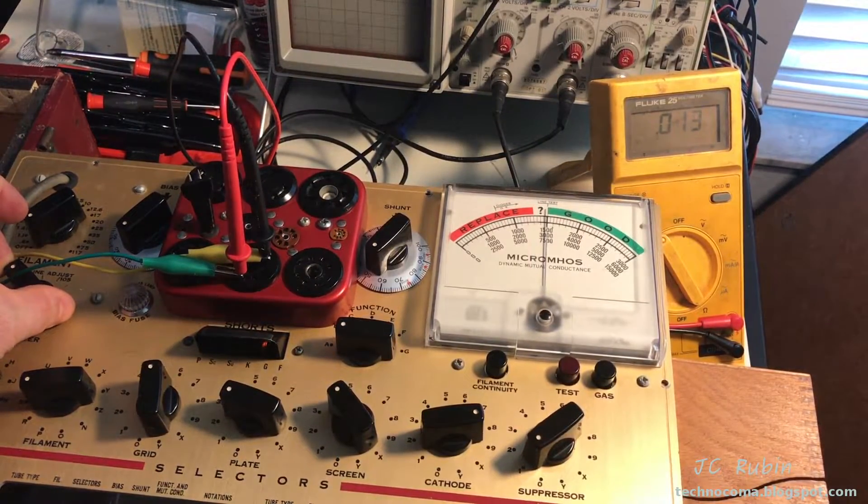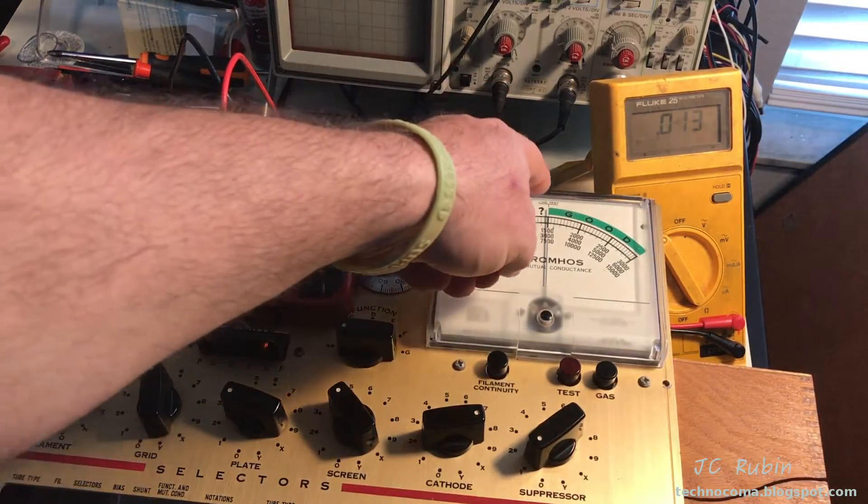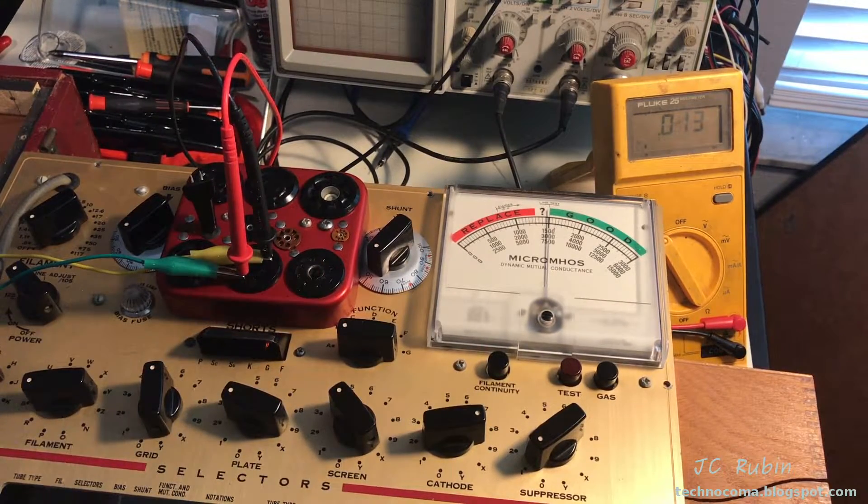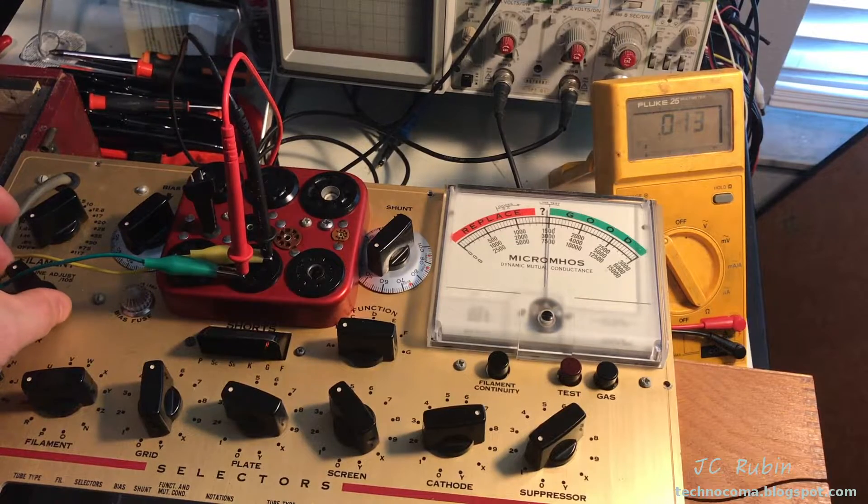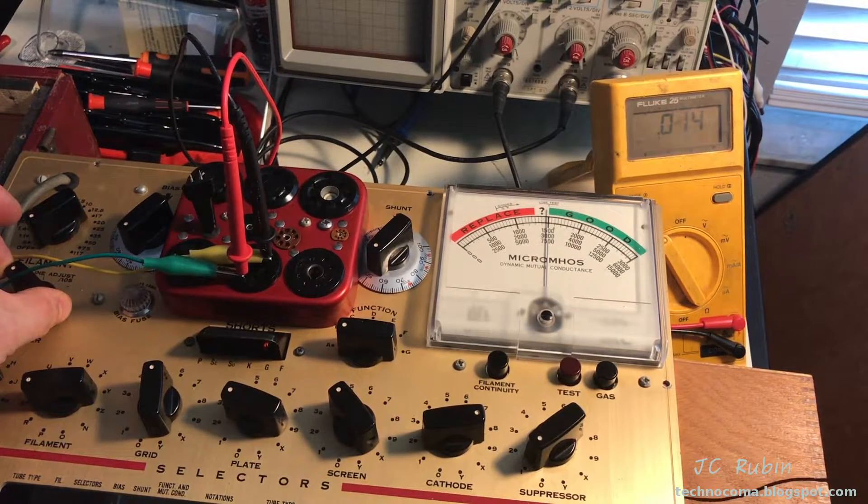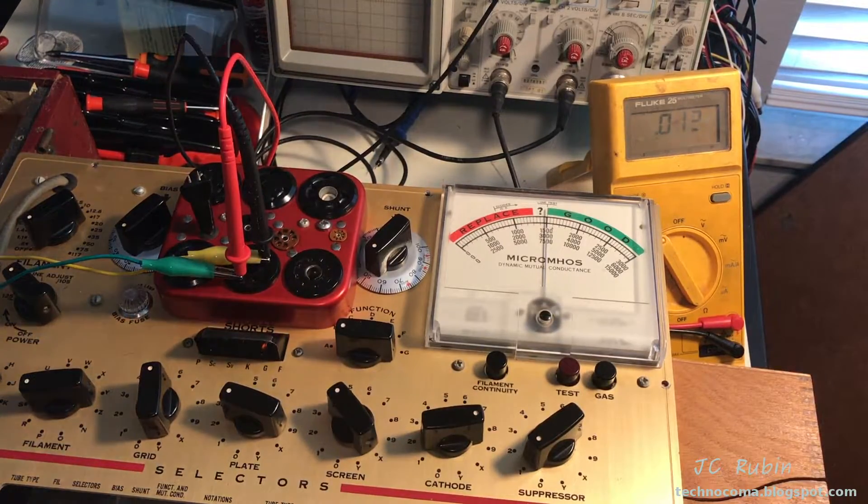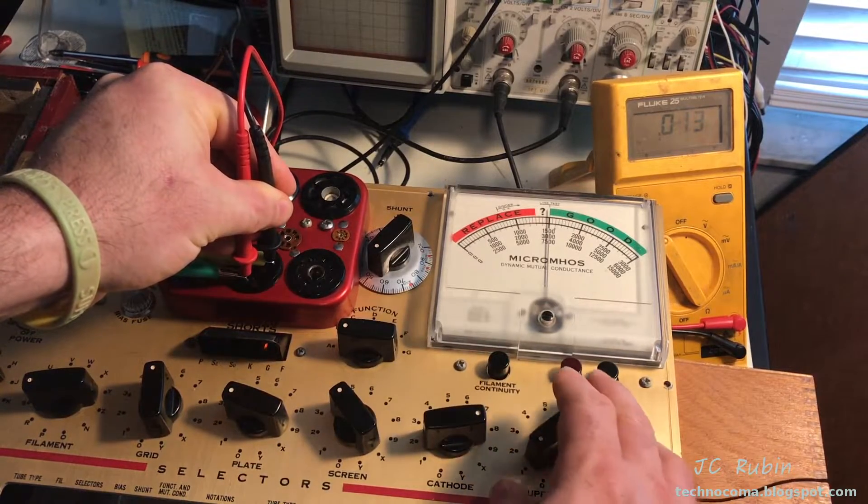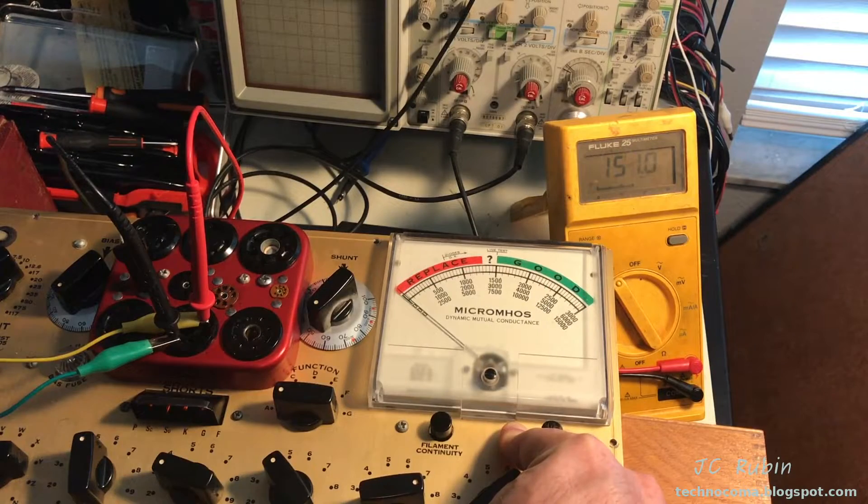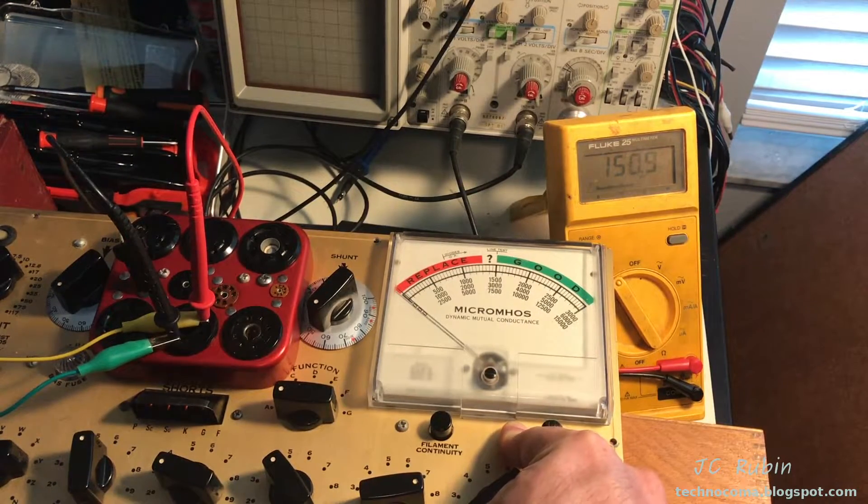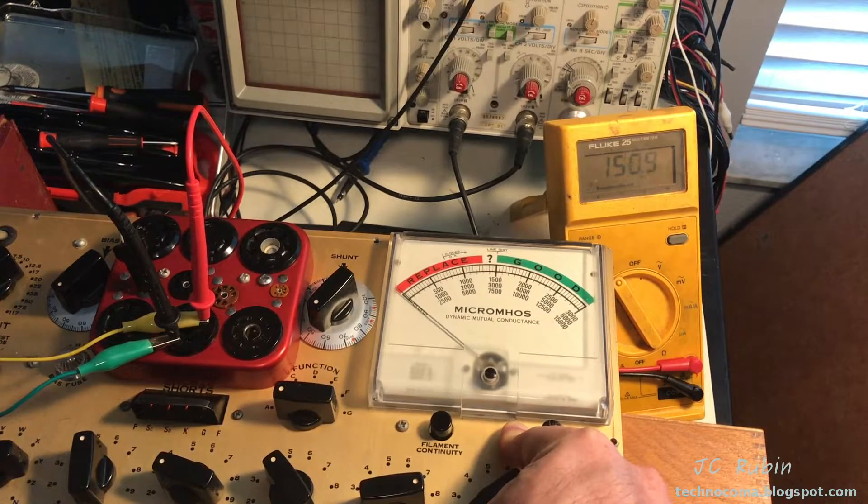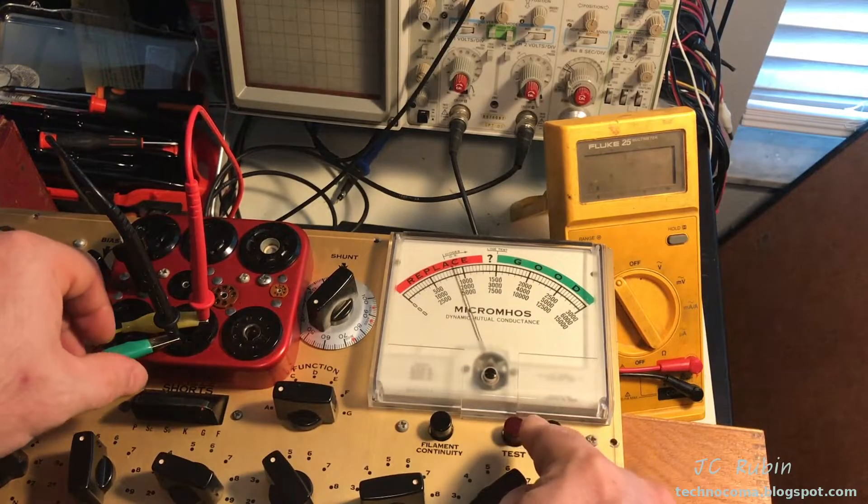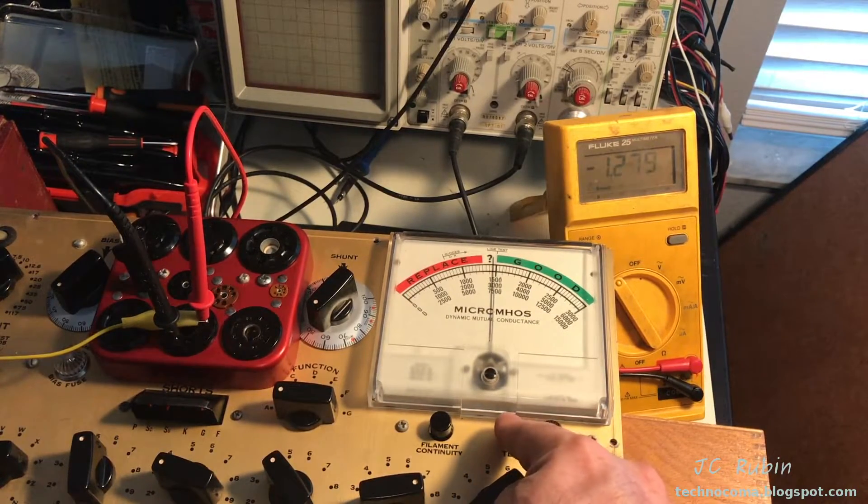First and foremost, before anything, make sure that line test is absolutely perfect. Once that's done, and because these are test probes, I like to push them nice and tight to make sure there's a good connection. Then I hit test and we're going to look for 150 volts on the Fluke. We can see that everything looks good at 150, 151. This voltage is well within tolerance for the plus or minus three volts on 150, so I'm not going to make any adjustment.